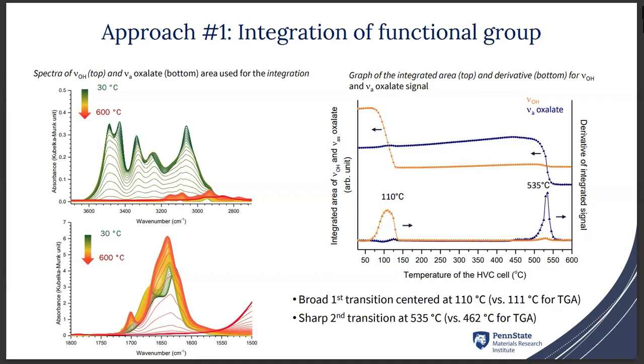So if we follow this integration over the range of temperature we set for the cell, we can see that for the hydroxyl, when we plot the derivative, we have a maximum at 110 degrees Celsius compared to the 111 given by the TGA. And when we look at the asymmetric stretching of the oxalate, we can see a change at 535 degrees centigrade, which was supposed to happen at 462. So we can already see that we have a huge disparity between the temperature we set and the actual temperature of decomposition we are probing by FTIR. One of the issues with this technique is everything needs to be done using a baseline, and the integration is subject to operator error. So everyone can integrate wherever they want and have a different result.